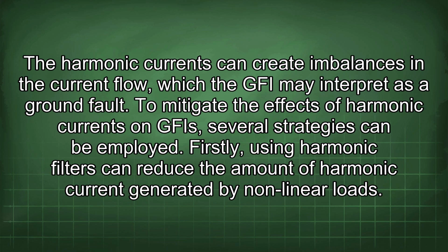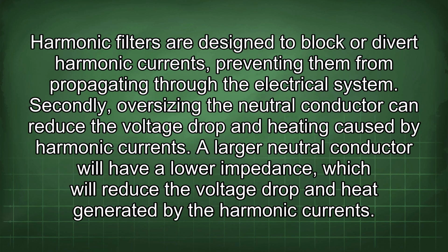To mitigate the effects of harmonic currents on GFI, several strategies can be employed. Firstly, using harmonic filters can reduce the amount of harmonic current generated by nonlinear loads. Harmonic filters are designed to block or divert harmonic currents, preventing them from propagating through the electrical system. Secondly, oversizing the neutral conductor can reduce the voltage drop and heating caused by harmonic currents. A larger neutral conductor will have a lower impedance, which will reduce the voltage drop and heat generated by the harmonic currents.